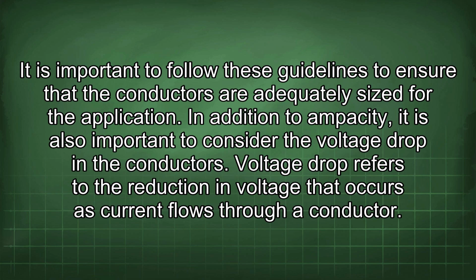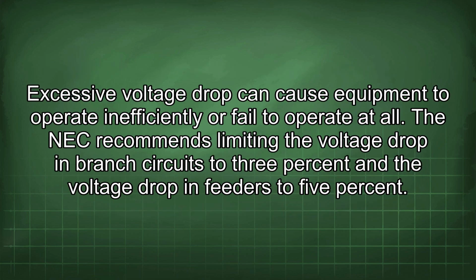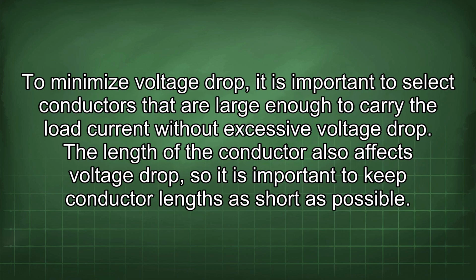In addition to ampacity, it is also important to consider the voltage drop in the conductors. Voltage drop refers to the reduction in voltage that occurs as current flows through a conductor. Excessive voltage drop can cause equipment to operate inefficiently or fail to operate at all. The NEC recommends limiting the voltage drop in branch circuits to 3% and the voltage drop in feeders to 5%. To minimize voltage drop, it is important to select conductors that are large enough to carry the load current without excessive voltage drop.